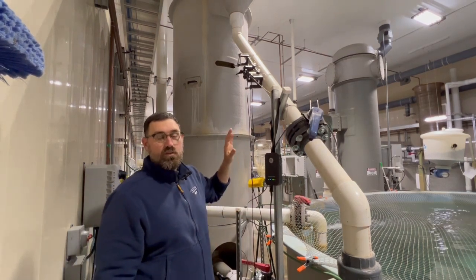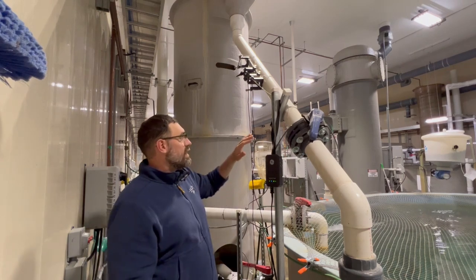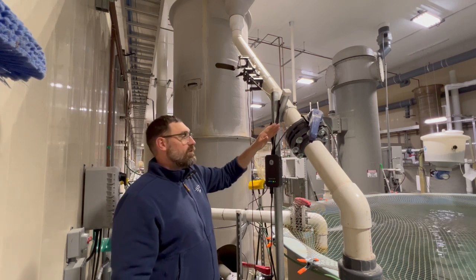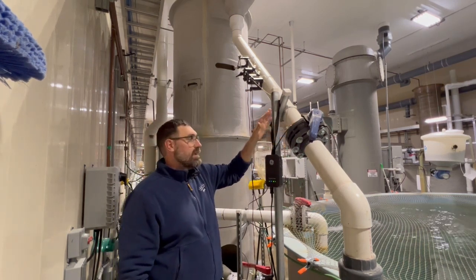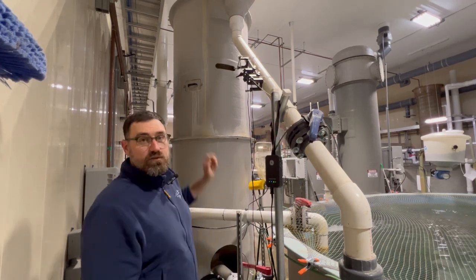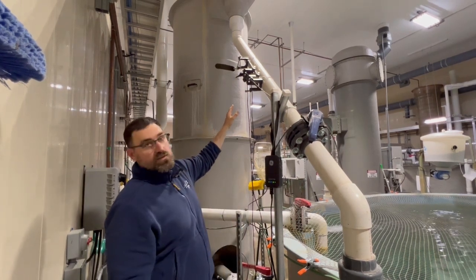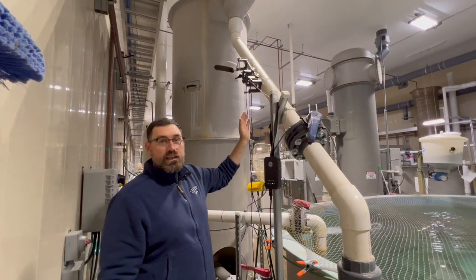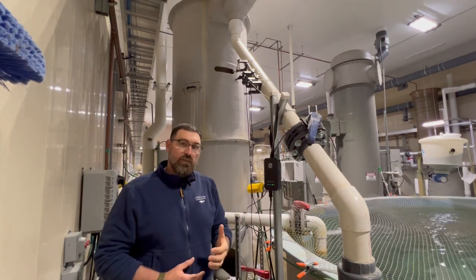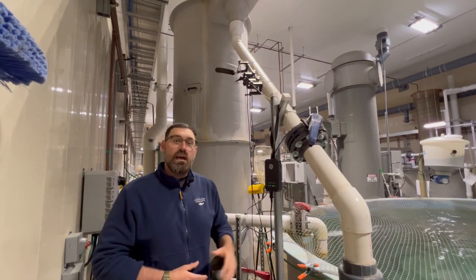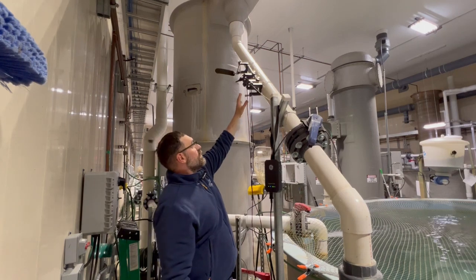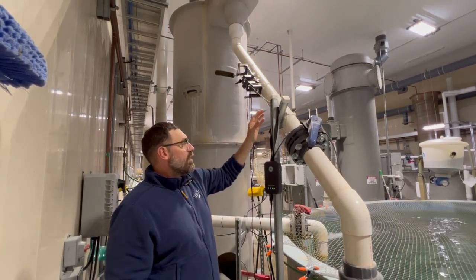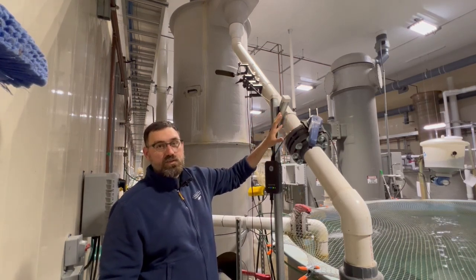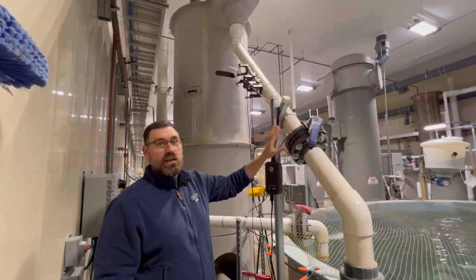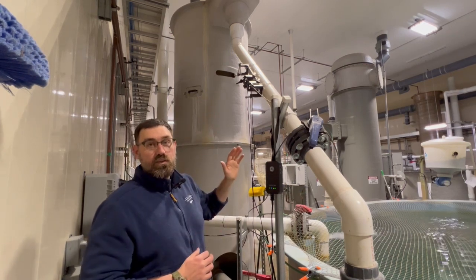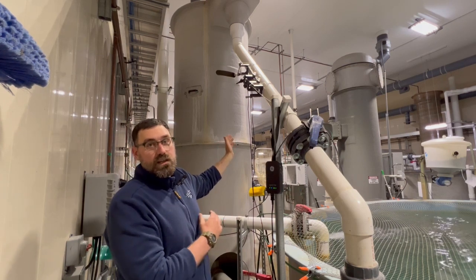When installing a flow meter on a pipe tank side, you want to keep in mind a few items. We want to install the flow meter on the straightest pipe possible with the fewest items on that line that are impeding the flow. So keep an eye out for valves and angled fittings or reducers. You want to make sure that the transducers are located on the side of the pipe and that the pipe is free of any kind of air. If there's air in the pipe, it'll give the flow meter a bad signal and we won't even get a readout. And lastly, we want to place the transducer bracket a minimum of 10 pipe diameters away from the closest 90-degree fitting or valve or any kind of impedance, and a minimum of 5 pipe diameters to the nearest angle fitting or impedance downstream.